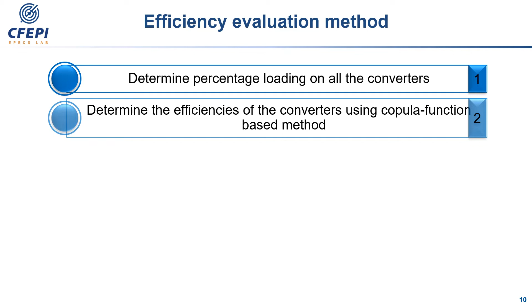The first step is to determine the percentage loading on all the converters. During the second step, efficiencies of the converters are evaluated using a Copula function based method. During the third step, power loss inside the microgrid is evaluated, followed by the efficiency of the microgrid. The next step is to calculate the weighted average efficiency during all scenarios considered in this study. And then, based on the results, the most feasible common bus type is selected. In this study, we have proposed a Copula function-based method to model the efficiency curves of the converters.